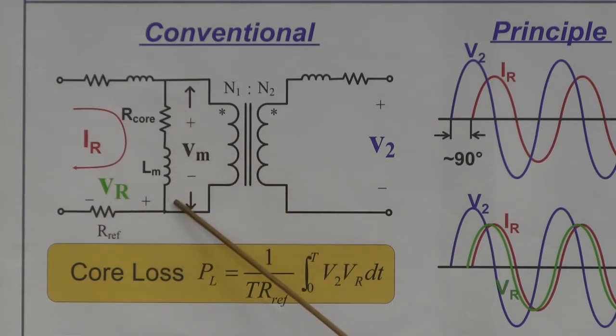Now we know the voltage and the current through this R-L branch, and by integrating the product of Vr and V2, we can get the core loss. This method is good because it automatically excludes winding loss.